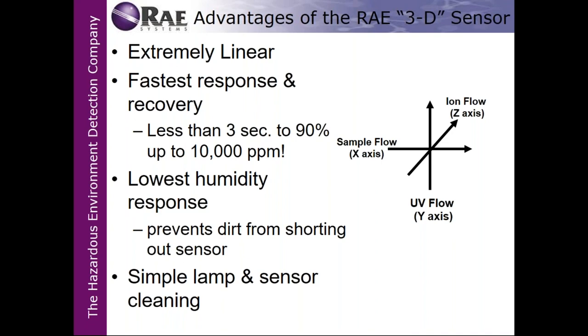Linearity, it's very important to understand what linearity means. It's the fast response and recovery. So less than 3 seconds to a T90 up to 10,000. Actually, in the MiniRAE 3000, it's 15,000. Lowest humidity response, prevent dirt from shorting out the sensor, and simple lamp and sensor cleaning. So the higher the reading gets, like if you get over 9,000 or 10,000, if you have that XY graph, you see the Z axis on it, it actually will start to expand outward. And that's called linearity.